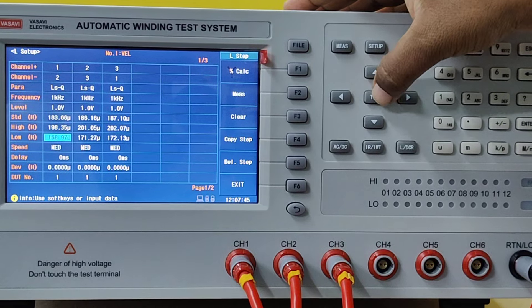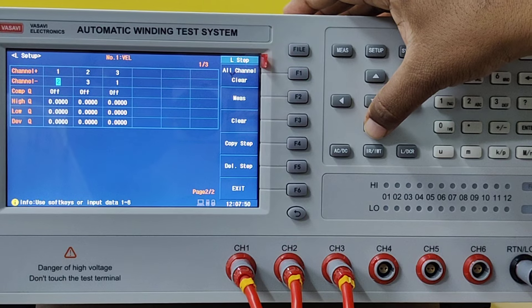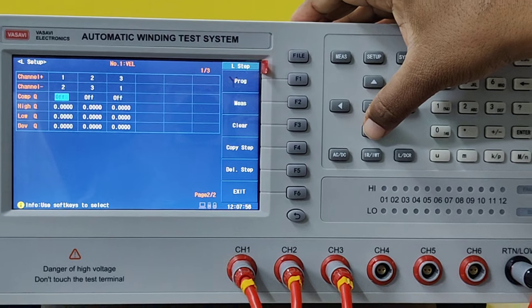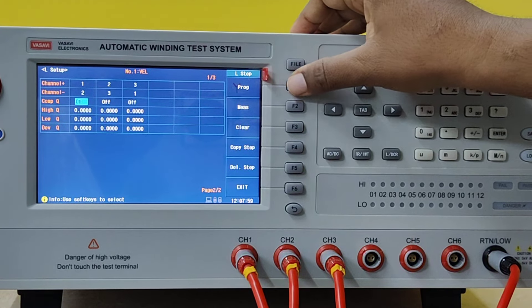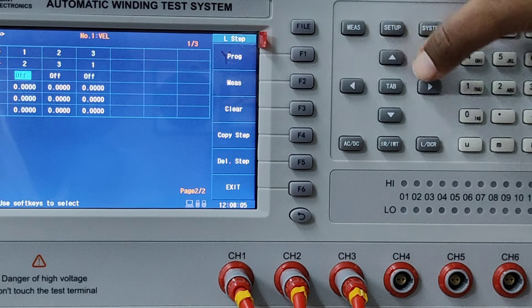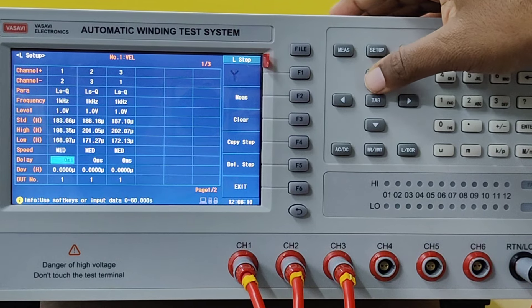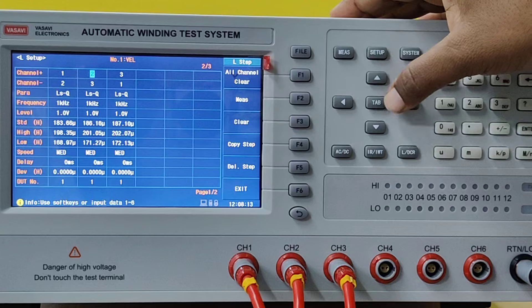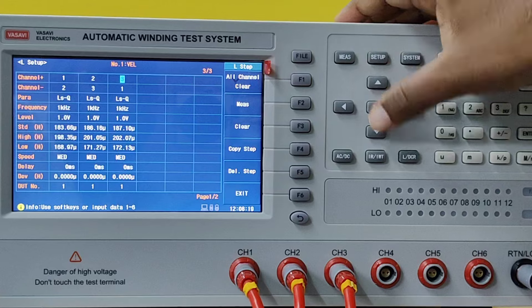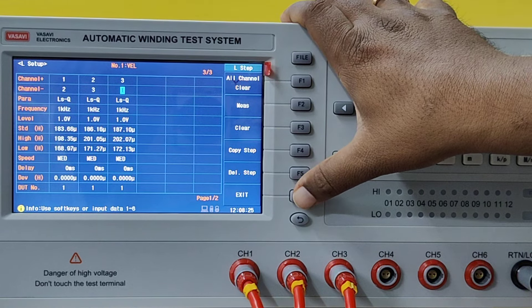Set the lower limit and upper limit. If you scroll down, you get Q. If you want to measure Q also, you have an option for selecting Yes or No. Yes means measuring Q is on; No means it ignores Q measurement. For the second winding, select channel 2 and channel 3, and for the third winding, channel 3 and channel 1, as it is a delta winding. Now all the parameters for inductance have been fed.